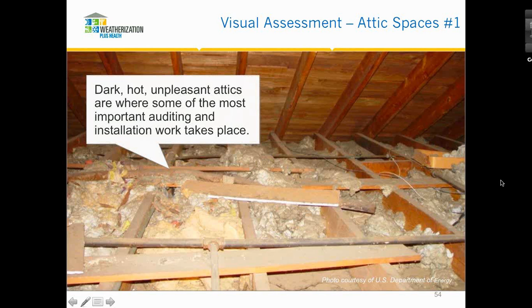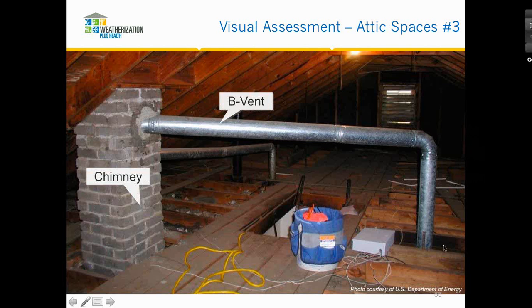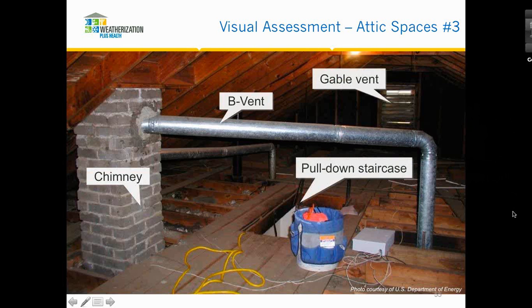This is where some of our most important work takes place at all levels, but especially during the installation. A lot of time is spent in attics. These are some of the things they'll note while they're up there. Is the chimney in good shape? Is it safely conveying those exhaust gases out? Is the vent, the flue, this looks like from a water heater, the proper kind for the appliance?